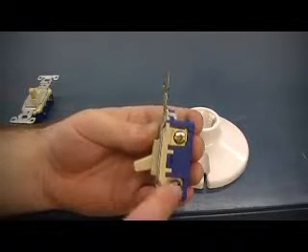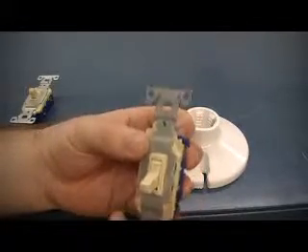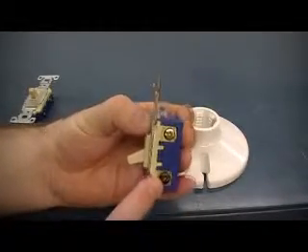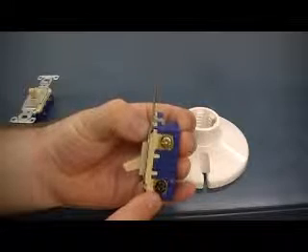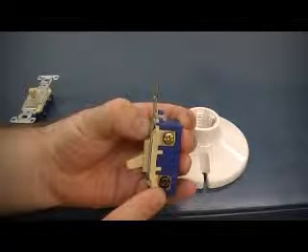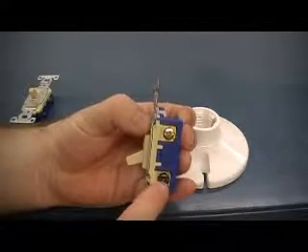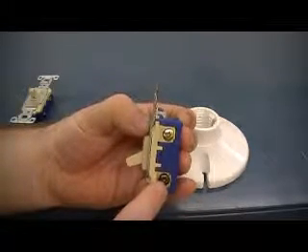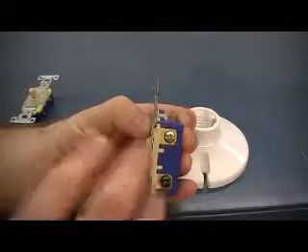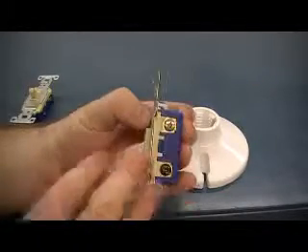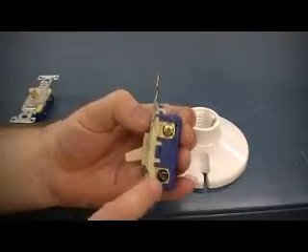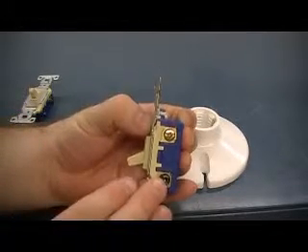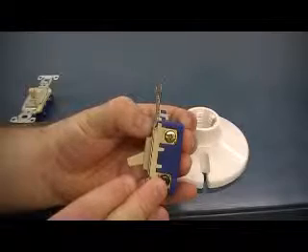Okay, it's the common point of this switch. Okay, so don't confuse that with the term neutral as common. Okay, so this doesn't mean that the neutral wire, which is also called common, connects to this switch. Okay, no neutral wire connects to this device. The term common here refers to the common point of the switch itself.